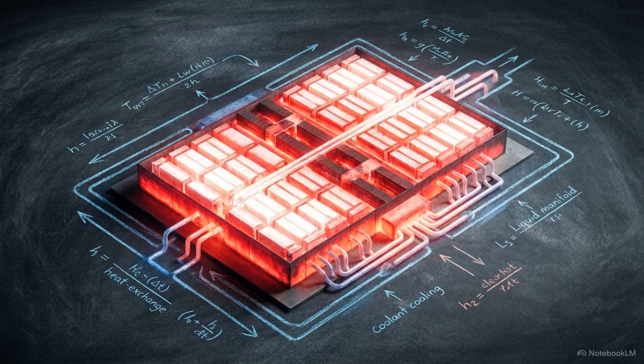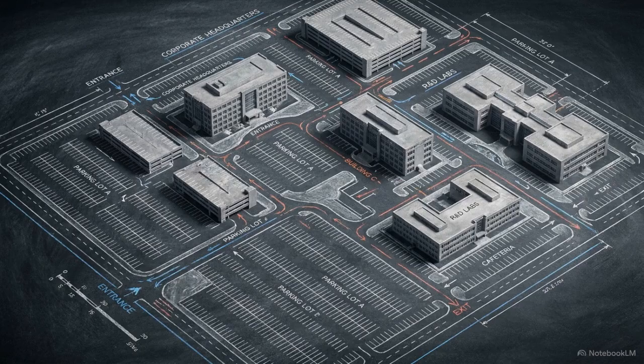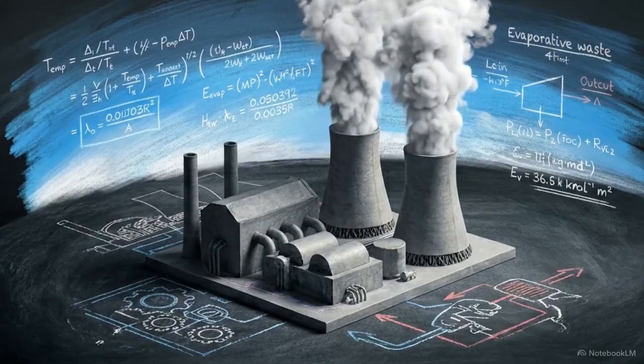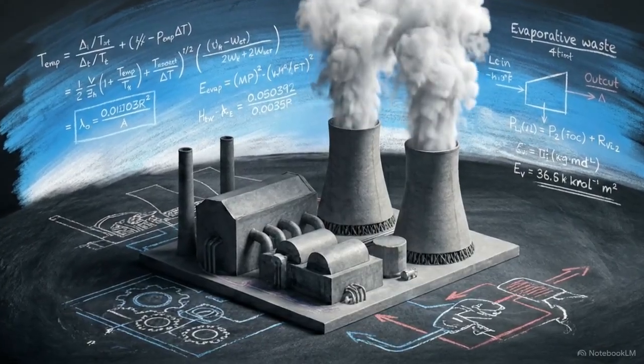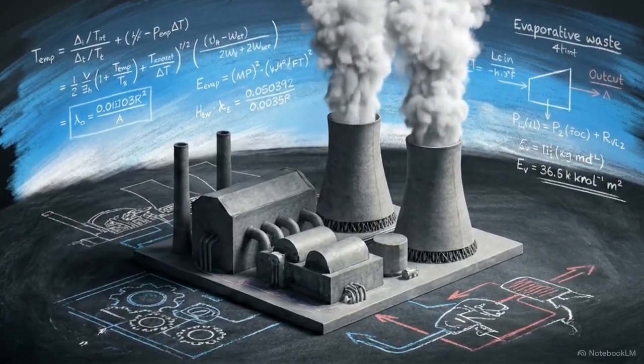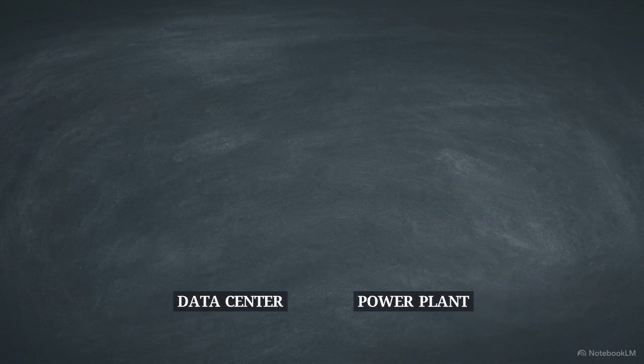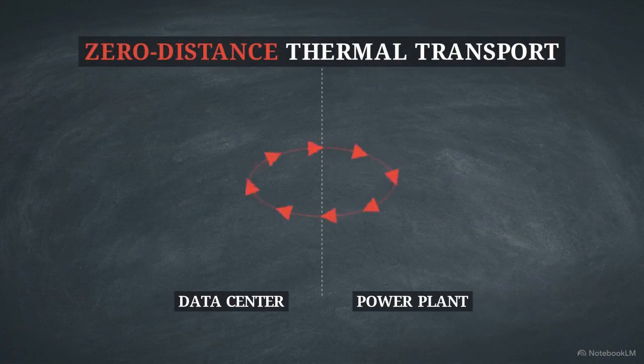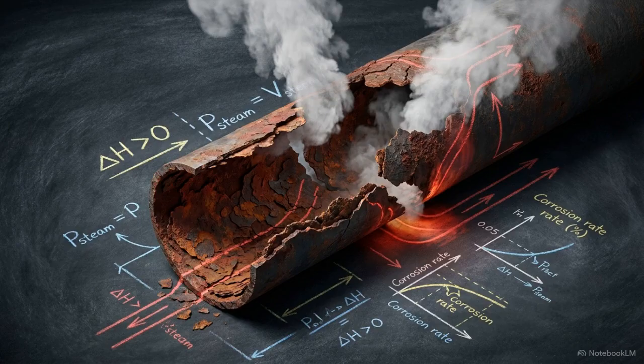A 10-megawatt hyperscale data center is a continuous, massive industrial heater, converting nearly 100% of its electrical input into thermal energy. Standard data centers sitting in isolated office parks rely on massive cooling towers, evaporating millions of gallons of treated water solely to vent that industrial heat into the sky as waste. Co-locating the facility directly at a generation node creates the physical advantage of zero-distance thermal transport, eliminating the degradation that ruins municipal district heating pipes over long distances.